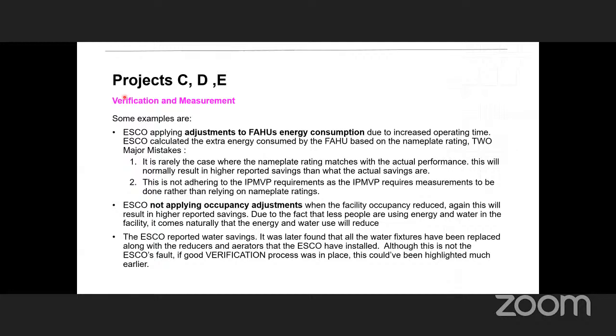Some other projects we've seen also had problems with the M&V. For example, an ESCO applying adjustments to fresh air handling unit energy consumption due to increased operating time. In this case, the ESCO used nameplate ratings rather than actual consumption. If you look at a nameplate, you'll find the motor has a certain kW rating, but that's the mechanical kW. So they used equations, like mechanical kW times some load factor, as the basis for the electric motor's consumption on that fan, instead of actually doing measurements and calculating savings more accurately.